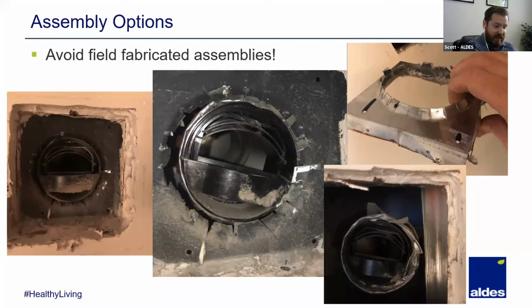And actually this assembly that I have sitting on my desk is a perfect example, because traditionally you would see the grill with the balancing damper mounted directly to the neck of the grill. That's all we're doing with this, right? We're mounting the airflow regulator directly to the neck of the grill to have an assembly that installs with the grill, so no different than any other grill on the planet, but it's adjustable through the louvers of the grill, so you can actually see in there, and you can make your adjustments with a screwdriver just like any other balancing damper on the planet, and it makes it that much easier to install, maybe make some adjustments in the T&B process. Very good.